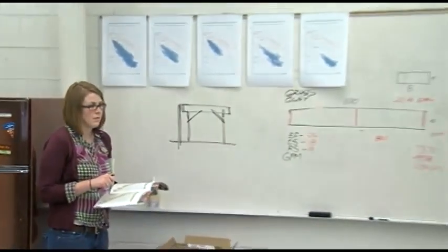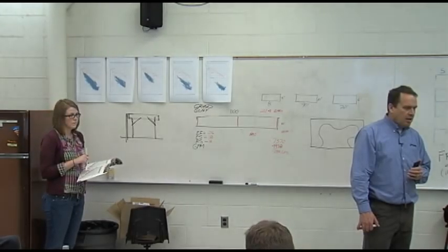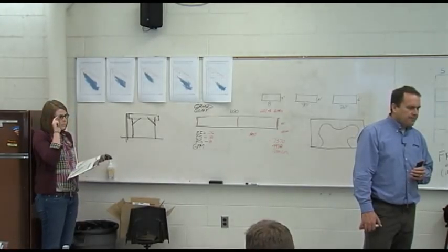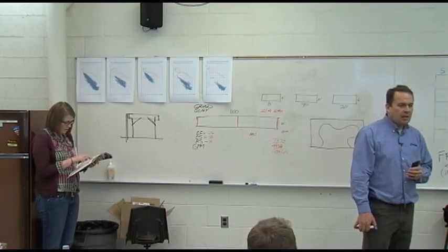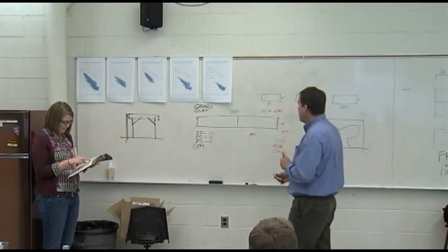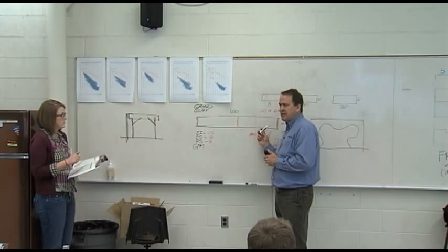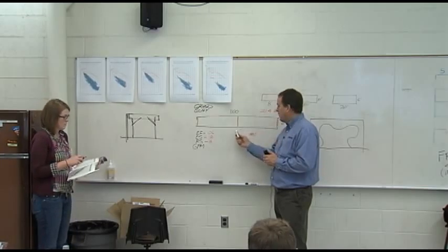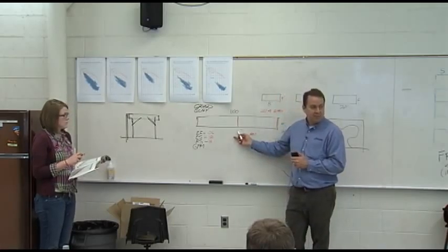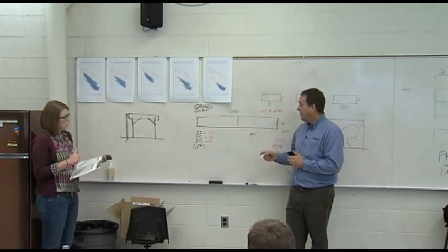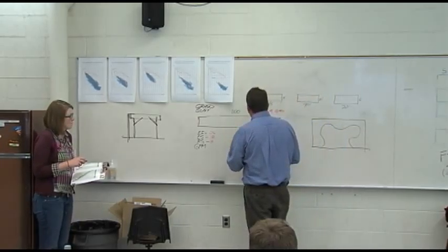He's using 7.5, but we go for 5. So it's 5 or 7.5, and you're saying it's typical to use 7.5. Yeah, so if it's 5 feet per second, what would the size of our pipe be? 1.25. Our supply headers and our exhaust headers are always the same size. So whatever sizes we're looking at, this will be 1.25 for 5 feet per second, or 1 inch on both of those.